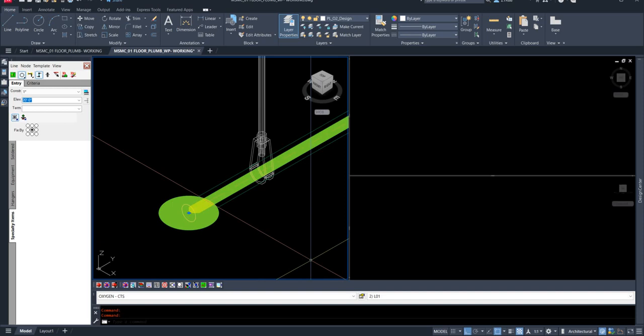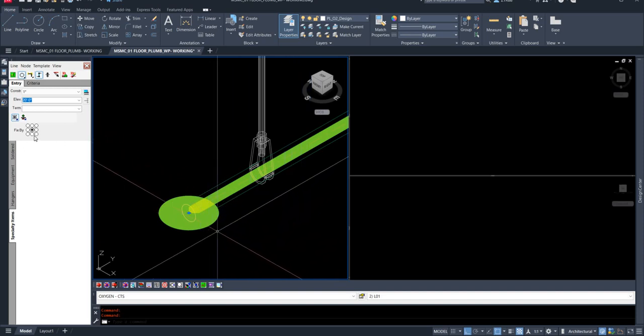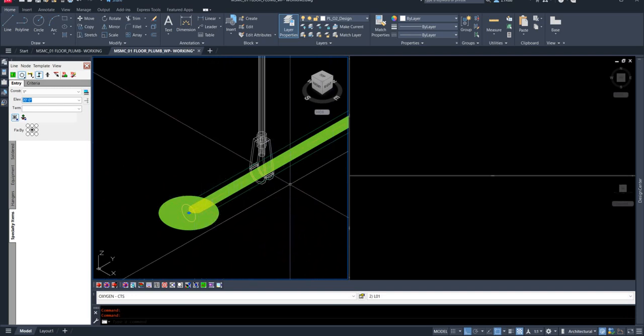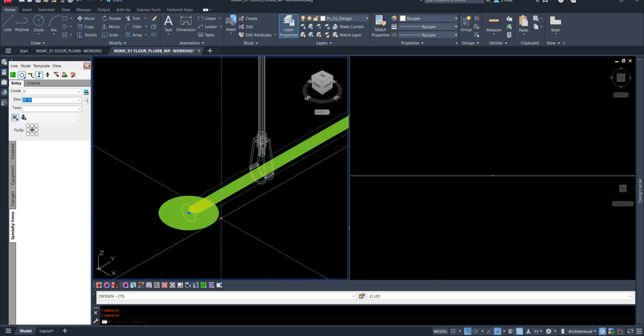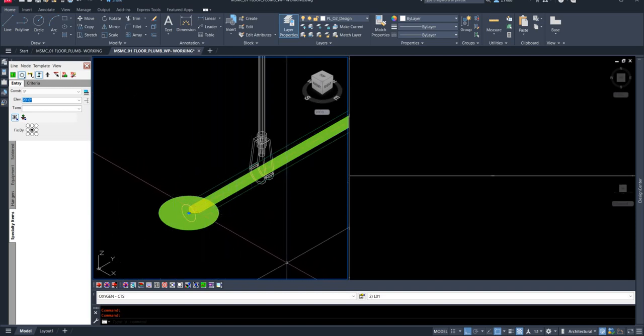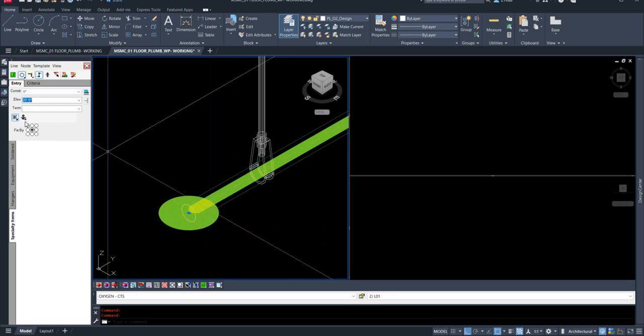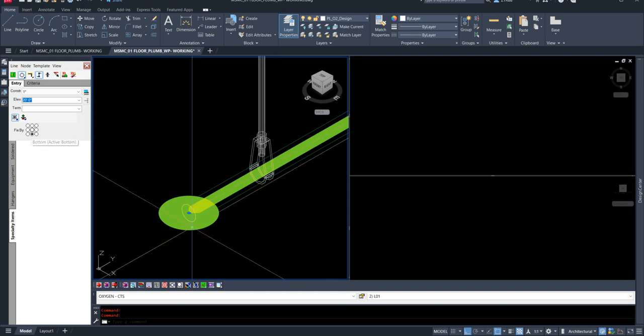So if you have a trapeze that's at 15 feet, this way, what I'm about to show you will allow you to set all of the design lines at that same 15-foot elevation, regardless of the pipe size, and they will all have the same bottom of pipe elevation. So to do that, when you're drawing the line, you would set it here. You would change that here. But this line has already been drawn.